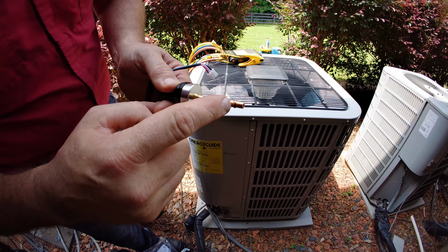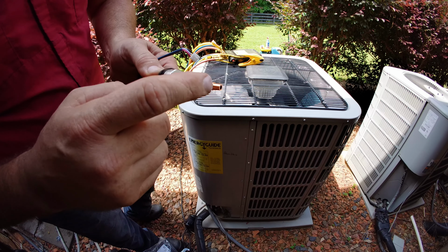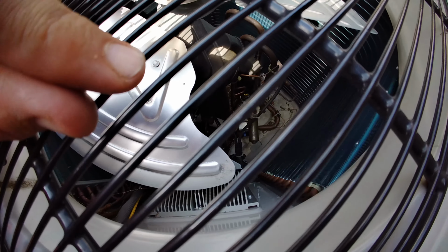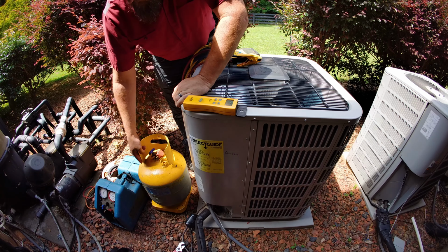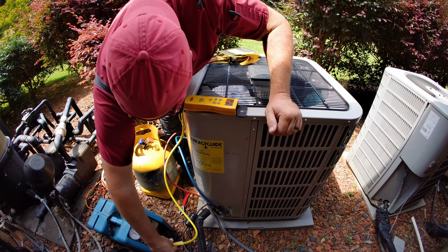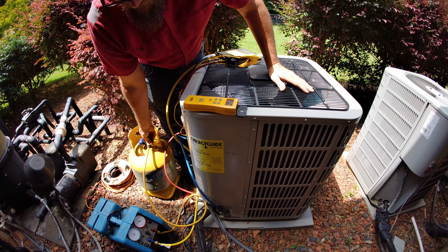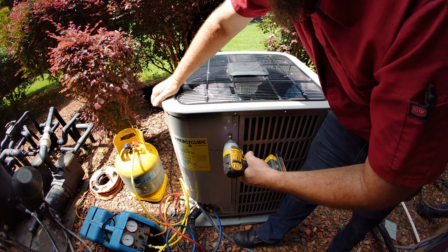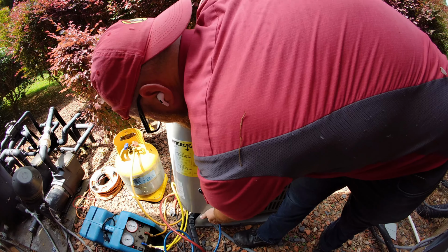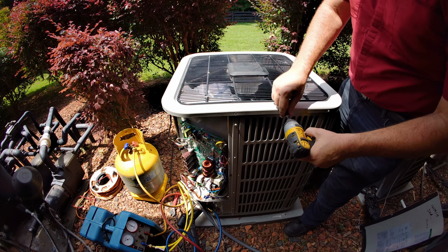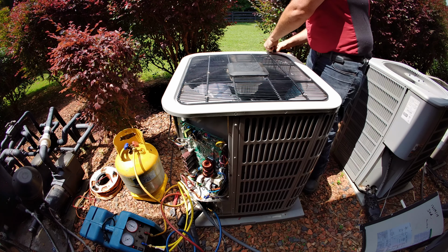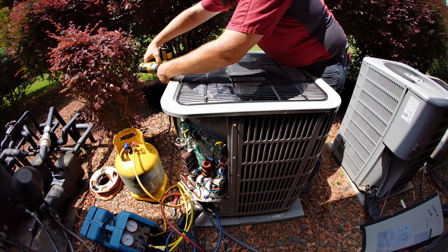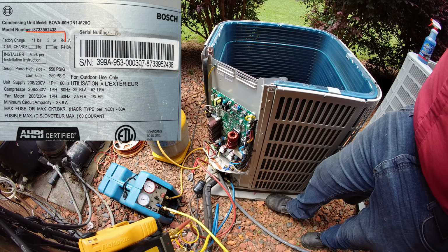The main problem we have with it is, as you notice, this is not a screw-on or flare, so we are unfortunately going to have to sweat out the original there, and to do that we'll have to evacuate this system. This guy down, it was holding just shy of 11.5 pounds, about 11 pounds 5 ounces. So pretty close to what the manufacturer specs said on it.